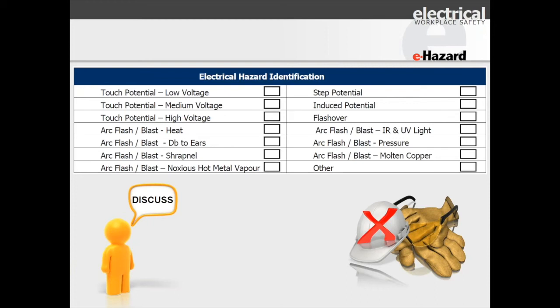The arc flash piece: radiative and convective heat, two different kinds of heat, dB to the ears. For personal protective equipment, you've got to be wearing hearing protection when there's an arc flash or arc blast hazard. It's very common to see people trying to put on a 40-calorie ensemble, for example, and you look — they're not wearing any hearing protection. They really need to break that down a little bit.